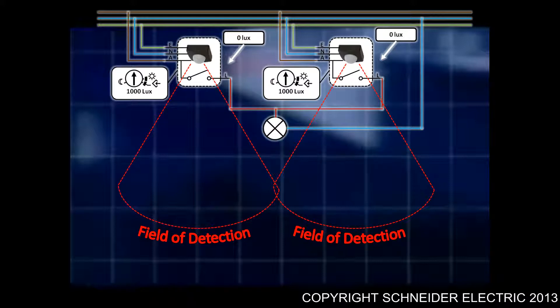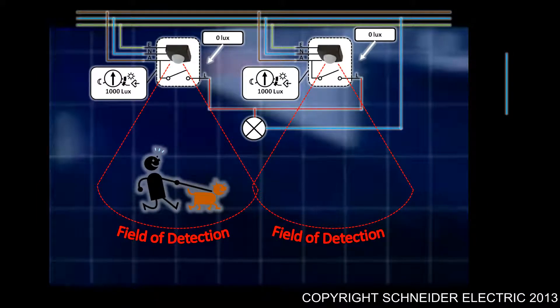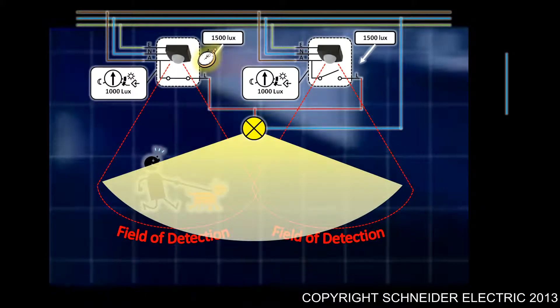Something else you need to take into consideration when positioning sensors is how you position sensors that are paralleled, controlling the same load, where the load is influencing the field of detection for both sensors. In this particular example, I have two sensors controlling a single load, and that load is in the area of the field of detection for both sensors. If I move into one of those areas, because there's not enough light, and both sensors are set to 1000 lux, because there is insufficient light and the sensor has detected movement, it turns the light on and starts its own internal timer.